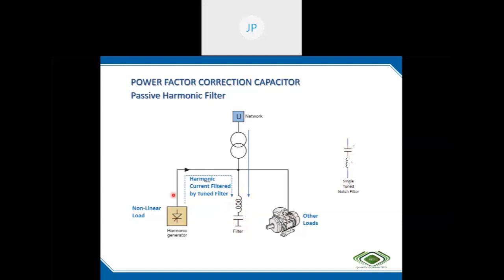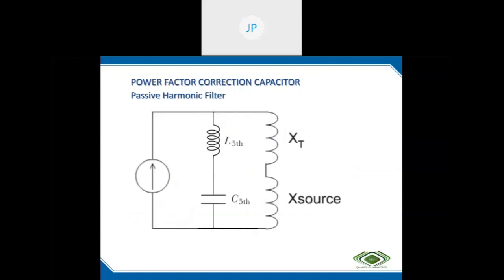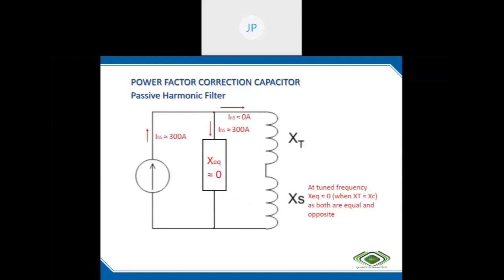So the entire injected current will flow through this one, and it will never go to the system, so there is no current injection into the system. So only fundamental current will be drawn from the system. Fundamental current for this, fundamental current for this, fundamental current for this. The harmonic source injection will be circulated locally. So the system is good. This is the simplified diagram. This is the equivalent circuit.